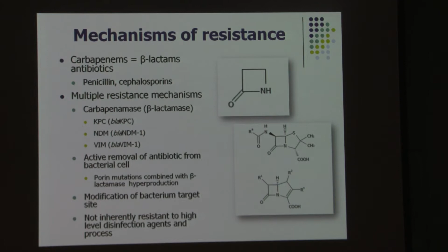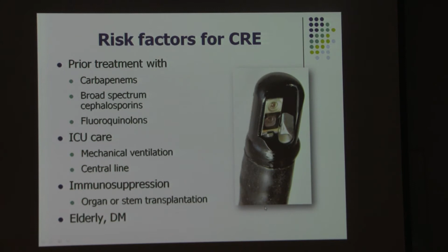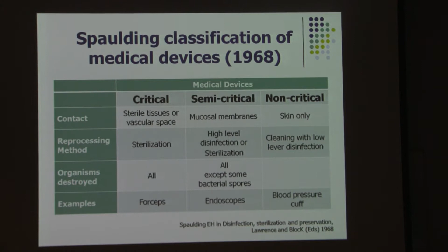So what are the risk factors for CRE? Clearly, prior treatment with carbapenems or other broad-spectrum antibiotics, ICU care, immunosuppression, elderly patients, and now duodenoscopes or endoscopes are another risk factor for CRE. Just as a reminder, endoscopes are considered semi-critical devices because they come in contact with mucosal membranes, and either sterilization or high-level disinfection is appropriate, and that should get rid of all organisms except for some bacterial spores. Alternatively, forceps would be considered critical devices as they come in contact with sterile tissues.